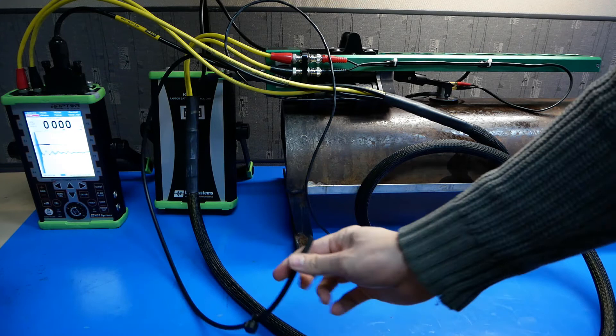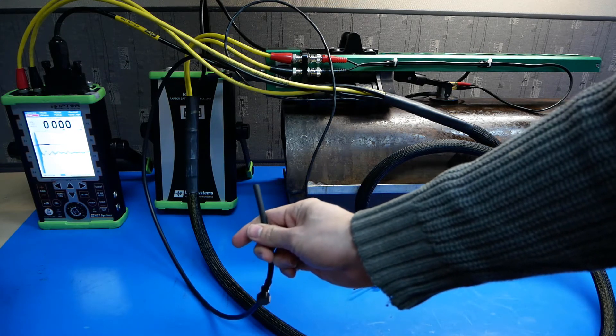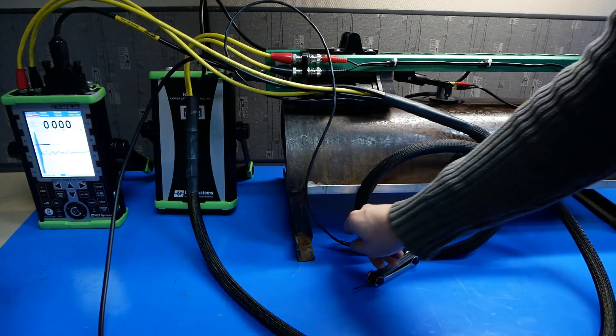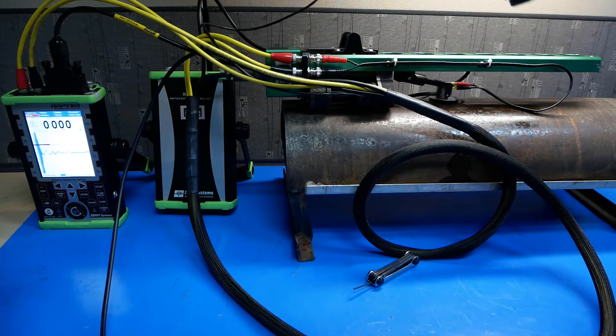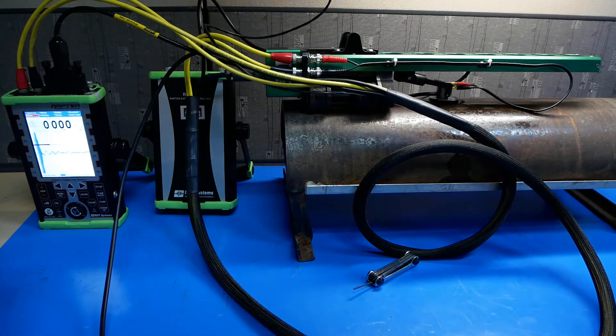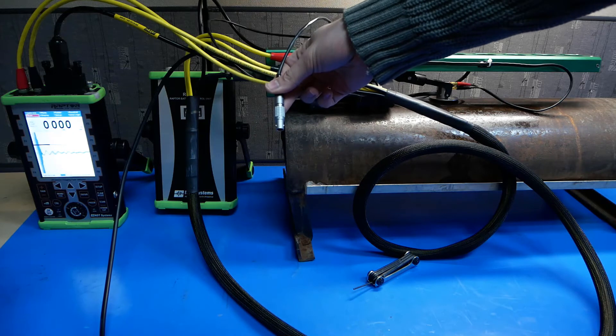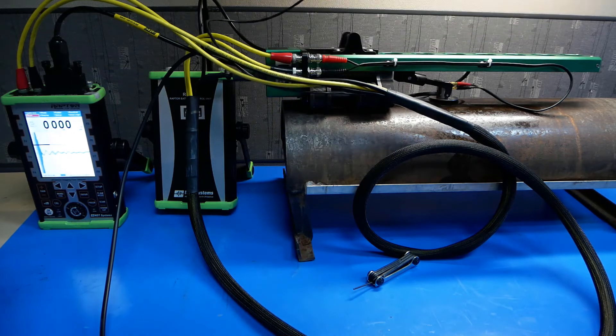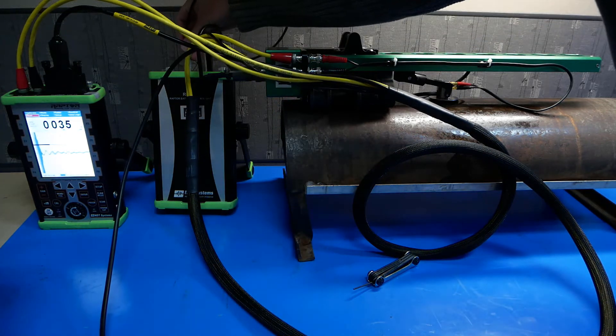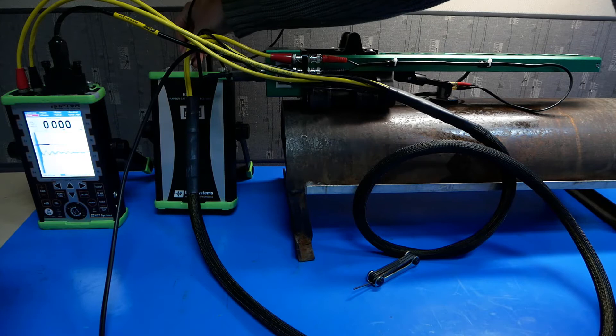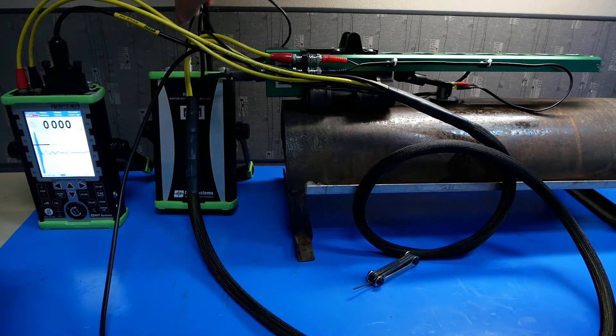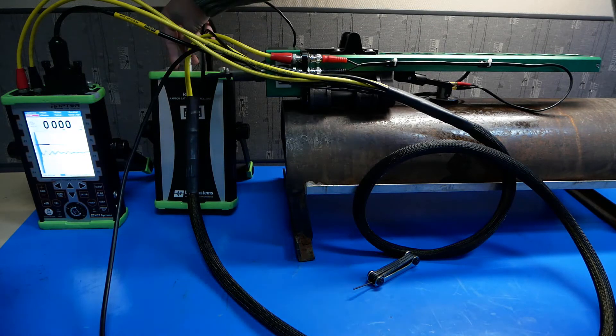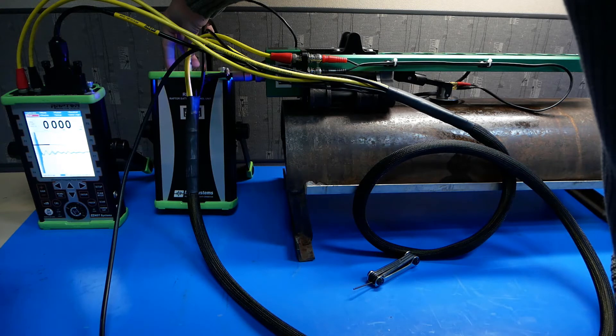Connect the feed tube from the other end of the RCA cable into your feed system. This will supply couplant to the probe. Finally, take your power connector and plug it into the top of the external battery pack where it says scanner. Then, go ahead and push the power button to turn it on.